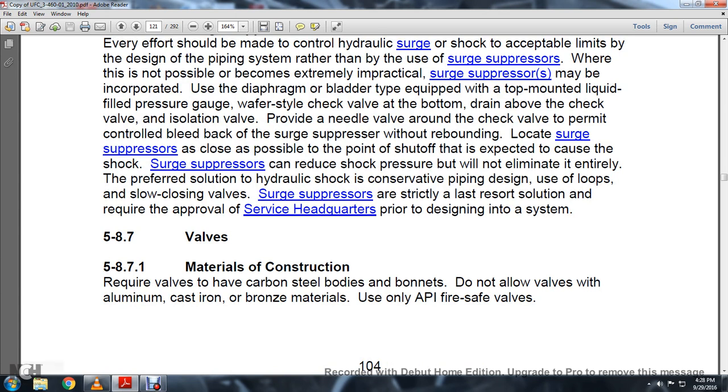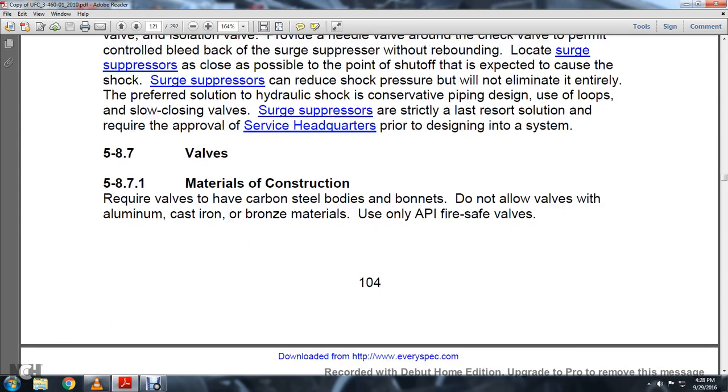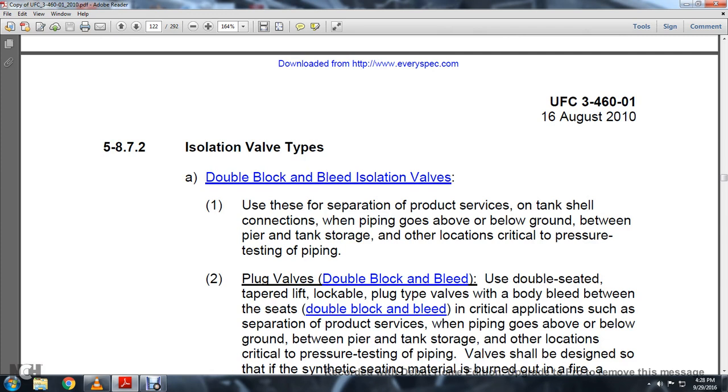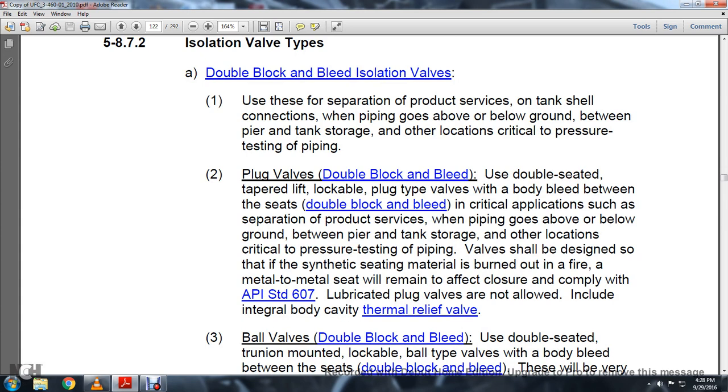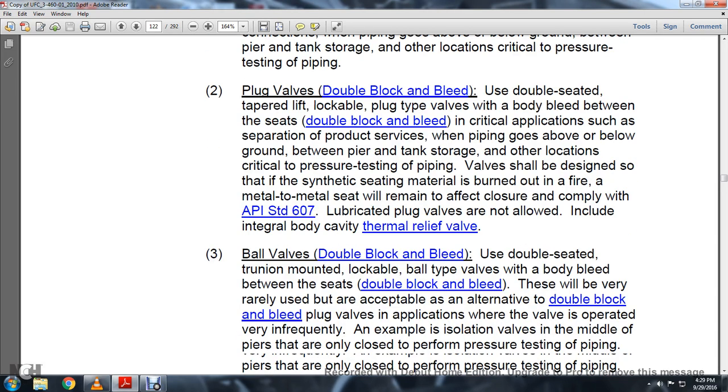Section 5.8.7 Valves. Section 5.8.7.1 Material Construction: Require valves with carbon steel body and bonnet. Do not allow valves in aluminum, cast iron, or bronze materials. Use API fire-safe valves for isolation applications. Use double block and bleed isolation valves to separate product service tank shell connections in piping going above and below ground between the pier and tank storage. Plug valves for double block and bleed applications should use double-seated taper-lift lockable plug-type valves with a body bleed between the seats. Valves should be designed so that synthetic seating material is burned out in a fire and metal-to-metal seat will remain an effective closure, complying with API Standard 607. Lubricated plug valves are not allowed.